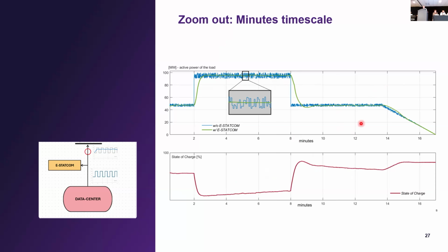It's in a minute time scale. So if there's a minute-time-scale ramp of a data center up and down, E-Statcom will not try to resist this type of ramp. What E-Statcom is for is to make sure there are no abrupt and quick changes happening within milliseconds. Like in these examples, if the load jumps or drops extremely quickly, what E-Statcom ensures is that it's no longer a jump, but a ramp. It's a more grid-friendly ramp which does not pose any risk to rotating equipment, and typically it's slow enough for gas turbines to follow.